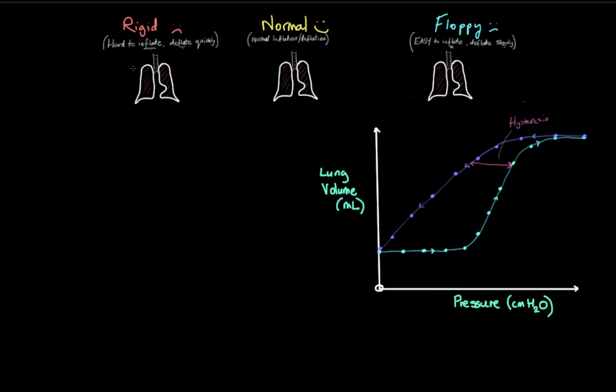Welcome back. In the last video we talked about the relationships between pressure and volume in volume control ventilation. We talked about how pressure varies as the properties of the lung change — how with rigid lungs the pressure generated by delivering a set tidal volume increases, whereas if the lungs become more floppy, the pressure generated is lower for the same volume. I said I would do a video on compliance, so that's what we're covering today, along with a pressure-volume graph.